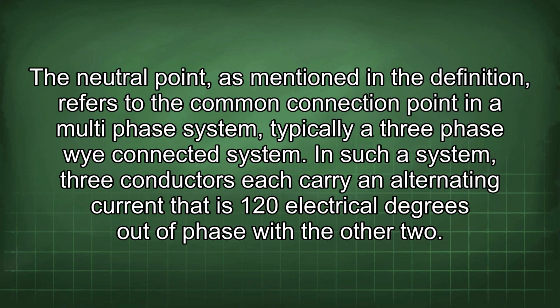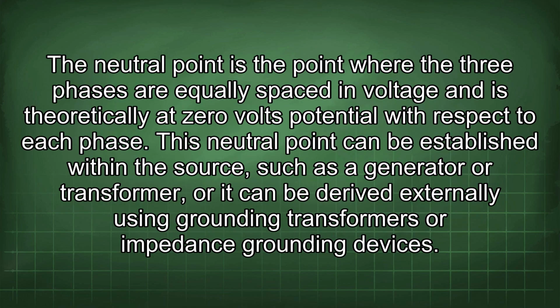The neutral point, as mentioned in the definition, refers to the common connection point in a multi-phase system, typically a three-phase Y-connected system. In such a system, three conductors each carry an alternating current that is 120 electrical degrees out of phase with the other two. The neutral point is the point where the three phases are equally spaced in voltage and is theoretically at 0 volts potential with respect to each phase.